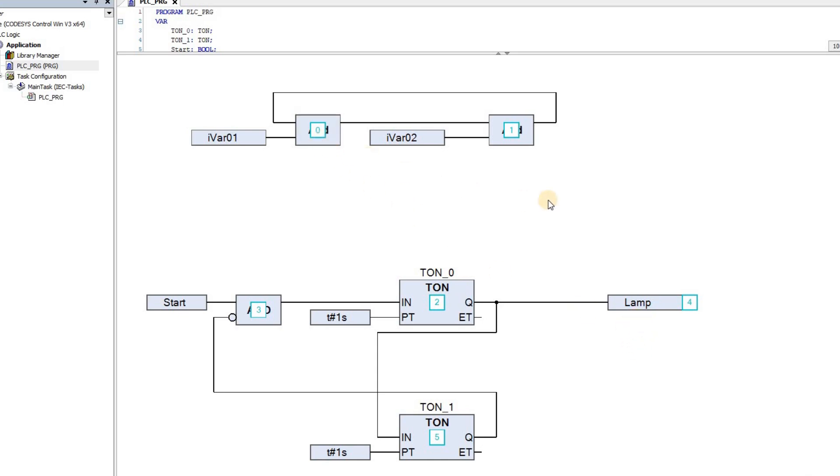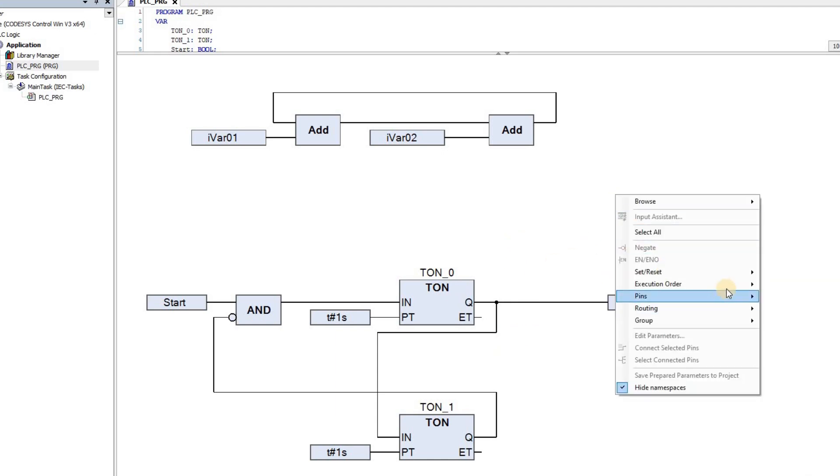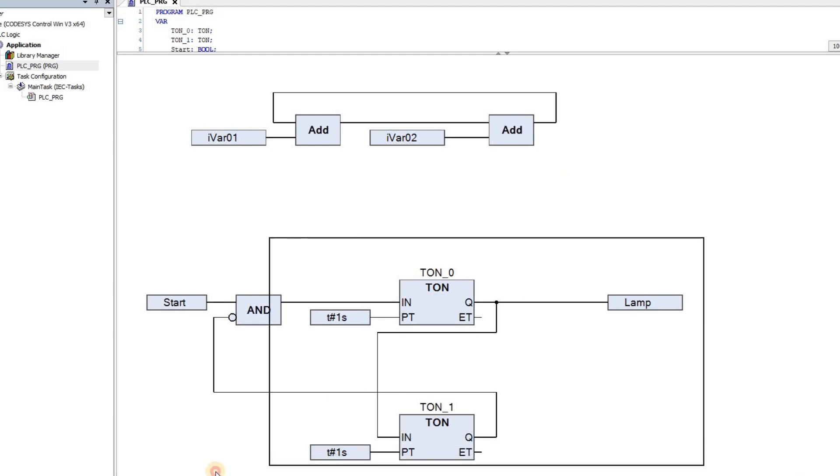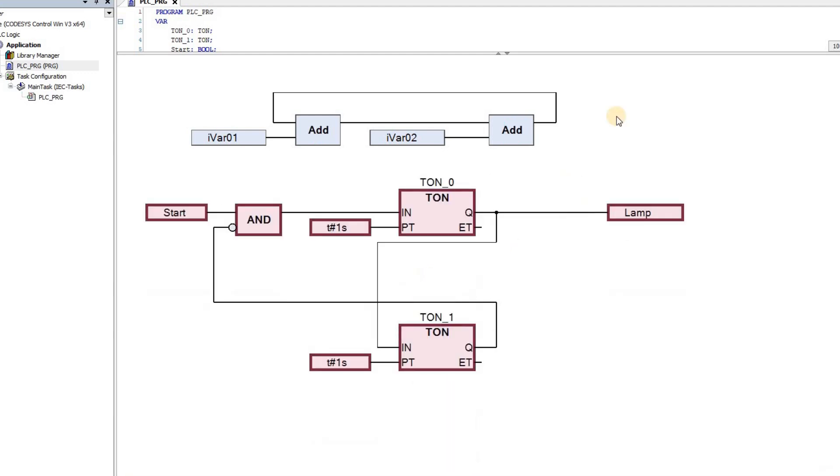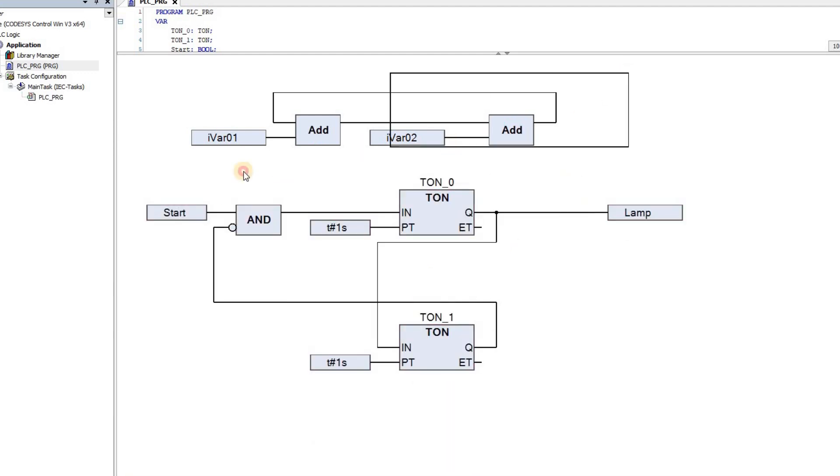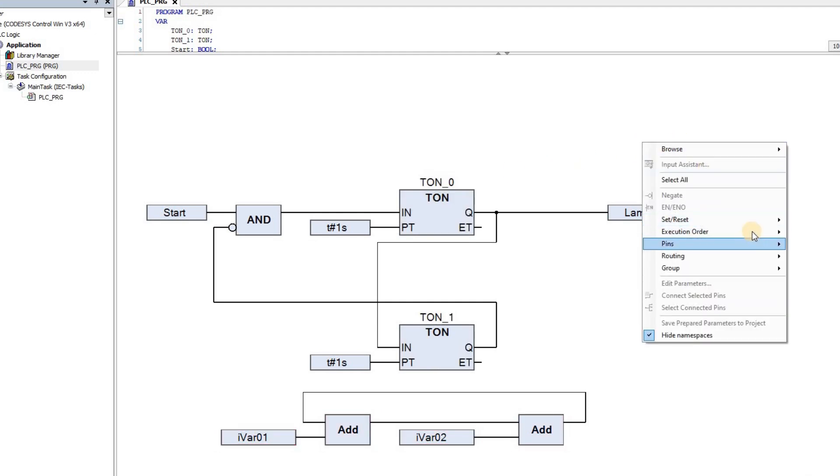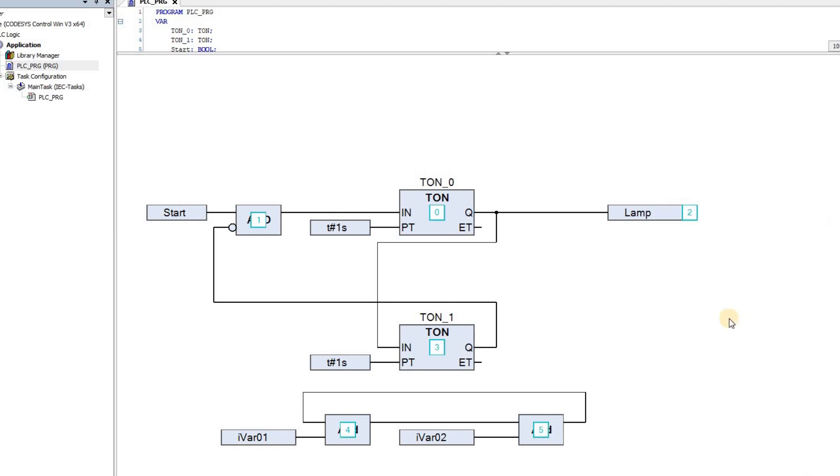You can see here that, if I move the networks around and change their topological order, the execution order changes as well. First, the network containing add blocks is on the top of the other one, and therefore it's being executed first, as seen by the execution order numbers. Then I change the topological position of the networks. I move the network with two add blocks below the other network with two on-delay timer blocks, and then double-check the execution order. Now you see that the network containing on-delay timers will be executed first, and then the other block will be executed.